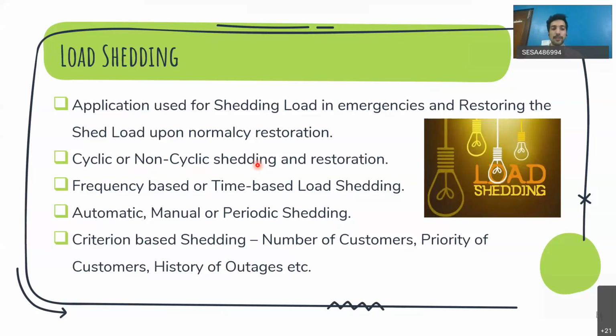Then all these types of shedding will be running on different criteria, like, for example, number of customers, priority of customers, history of outages, etc. So for example, you have 10 feeders to shed. The feeder which has the maximum number of consumers will be shed at the last. You consider this number of customers criteria. The more the number of customers, you don't want to shed it, so you put it at the last.